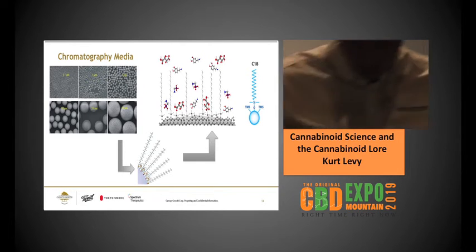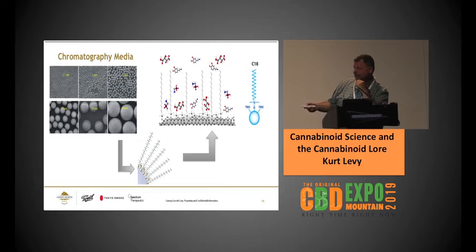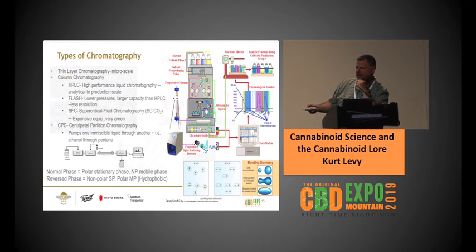The systems are really quite simple. It's reservoirs of the mobile phase, a pumping unit, and a unit that has a little loop where you can fill your sample in, and it introduces that sample plug into the flow path. It goes through the column. They separate, and then it goes through this detector, which just shines a light beam through a flow cell, and when compounds absorb the light, it makes a little peak on this chromatogram. Once we see the peak, we use a robot then to transfer the outflow to these various vials and containers, the fractionation. So at the end of the day, every 10 to 15 minutes, we're injecting a plug, and these bottles fill up. We get purified compounds.